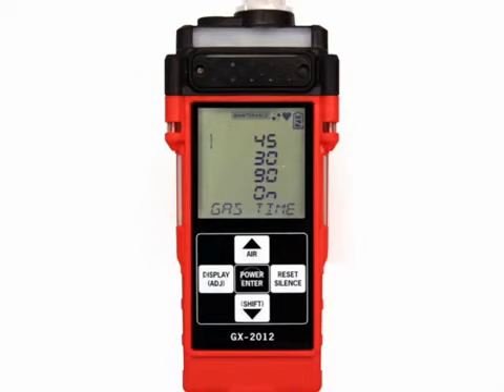To update the bump test tolerance, use the Shift button to scroll to the check value. The factory setting is 30%. This is the bump test tolerance value that is represented as a percentage. It is the percentage that the bump test reading can differ from the actual gas concentration. If the bump test reading differs more, the bump test will fail. With the cursor next to the check value and check displayed along the bottom of the screen, press and release Power Enter. The value will begin to flash. Use the Air or Shift buttons to select a new threshold value. The available values are 10, 20, 30, 40, and 50. Once a value is selected, press and release the Power Enter button to save it. The value will stop blinking.